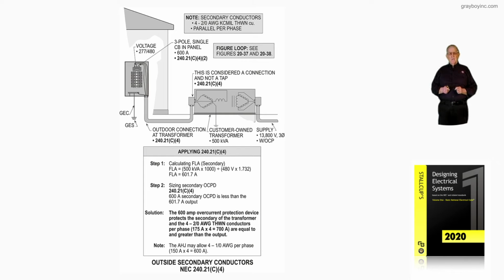Now this illustration deals with outside secondary conductors tapped off of the secondary side of a transformer. Before we get too deep into this illustration, let's review the note at the very top of the illustration. And notice we have secondary conductors and we have 2-aught conductors, THWN, copper, parallel 4 times per phase.